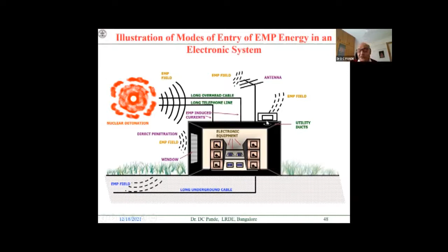If it is a shielded enclosure, if the shelter is a shielded enclosure, then for all these cables going in, we provide a terminal protection device for these cables. We provide EMP filters - EMP filters meaning both non-linear and linear filters. Then we provide honeycomb filters for the ventilation. Then we provide doors with finger strips, with shielded EMI gaskets and other such things. So this is the way it is done.